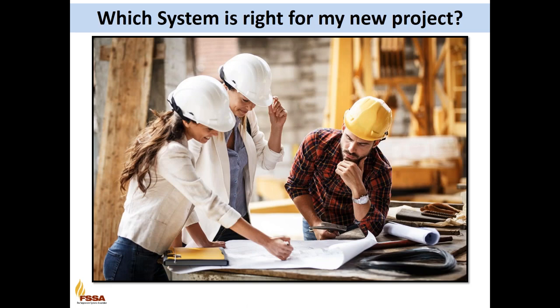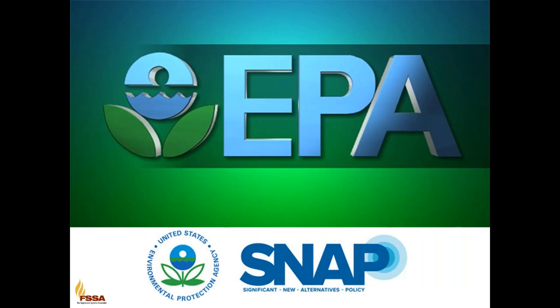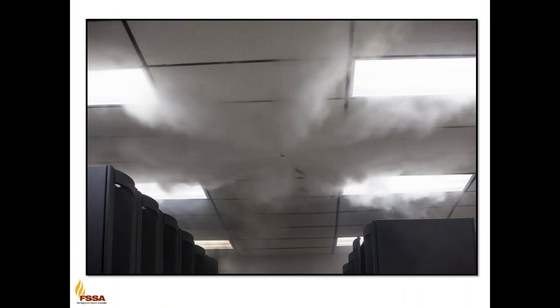Several acceptable halon alternatives have been developed by FSSA manufacturer members. The choice of today's modern clean suppression agents are divided into two major categories, halocarbon clean agents and inert gas clean agents. We will talk about each of these and their distinct characteristics. It is important to note that regardless of the way each agent is applied and how it goes about suppressing a fire, each is listed as approved on the EPA SNAP list.